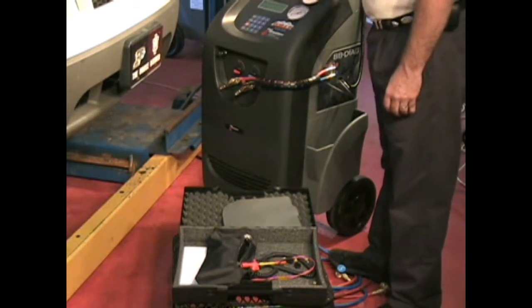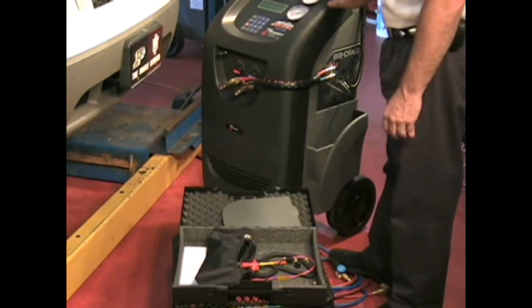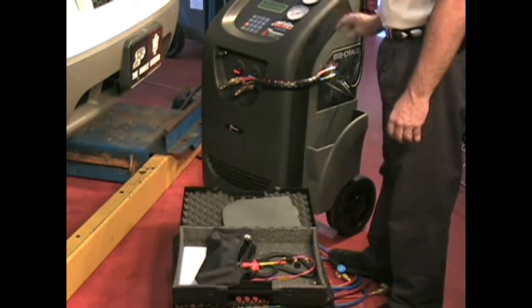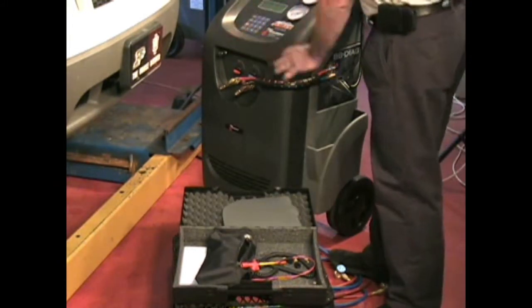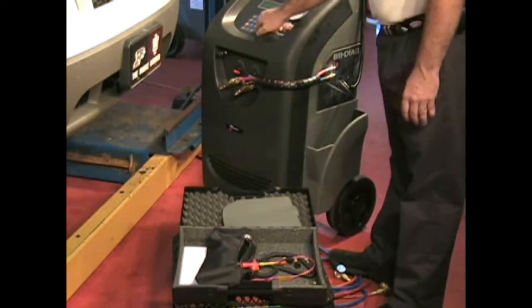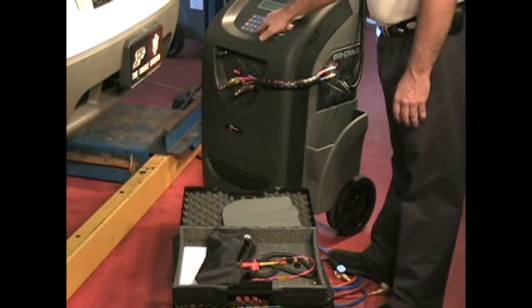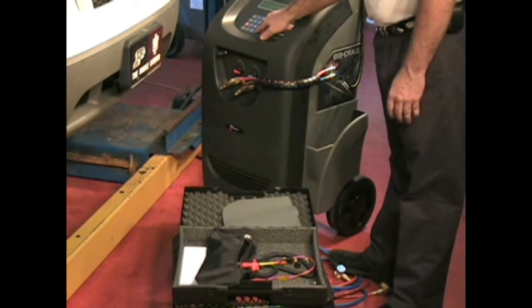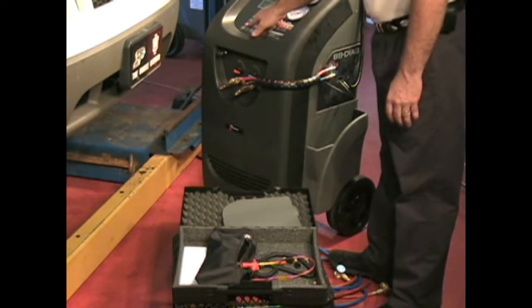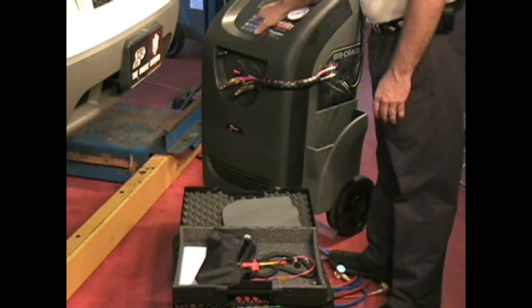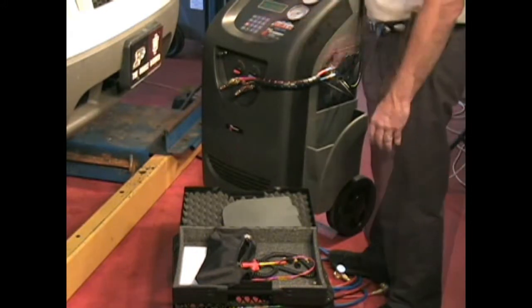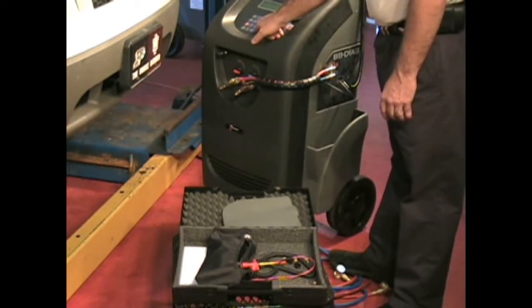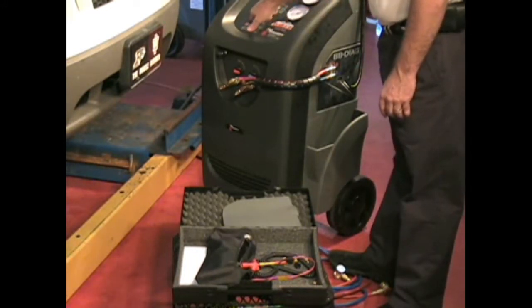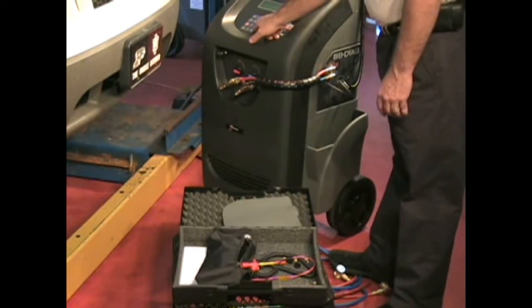If any of the sensors are reading inaccurately, calibration will be necessary. To calibrate, press Reset, then go back to AC Diagnostics. This time select BB-Diag Calibration. Enter 0791 and press Enter. Select the item needing calibration and press Enter. Simply enter the correct data and press Start.